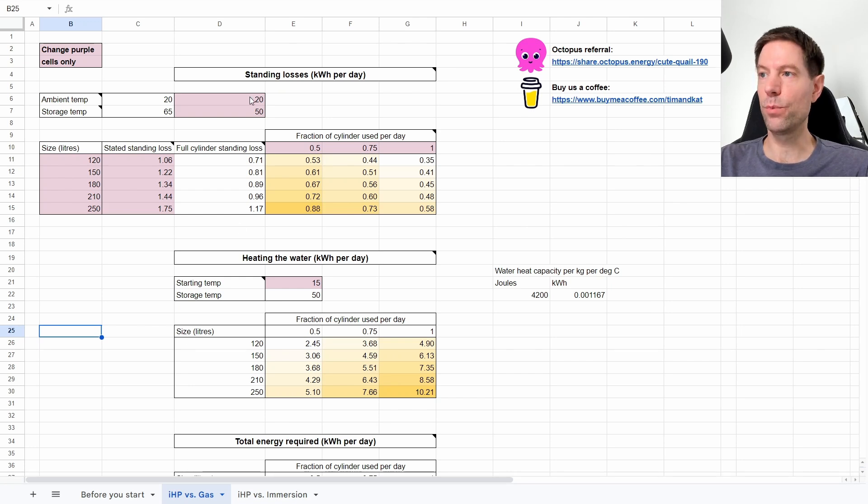So let's start by assuming that you've got your cylinder installed in an airing cupboard and the ambient temperature in that situation would be 20 degrees, so that's what we've got here and that's what I assumed in my original video. I also assumed in the original video that the average starting temperature of the water going into the cylinder is 15 degrees, and that's an average between winter at about 10 degrees and summer of about 20 degrees.